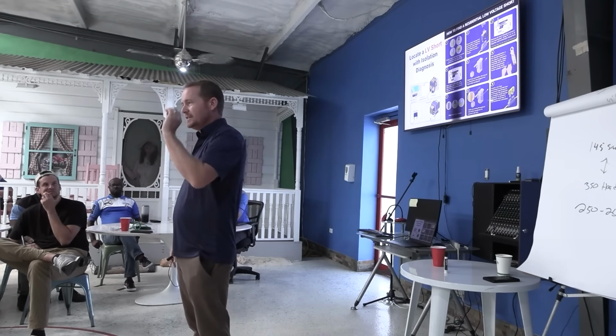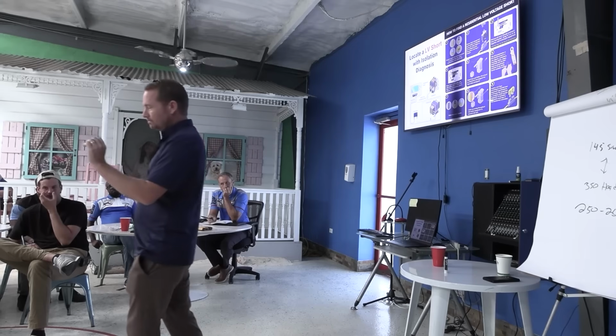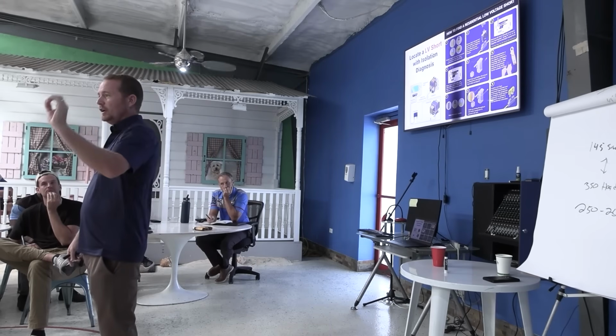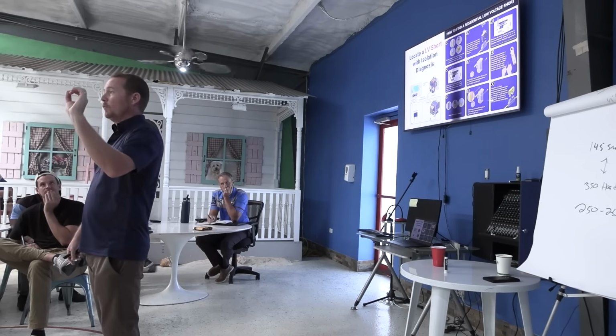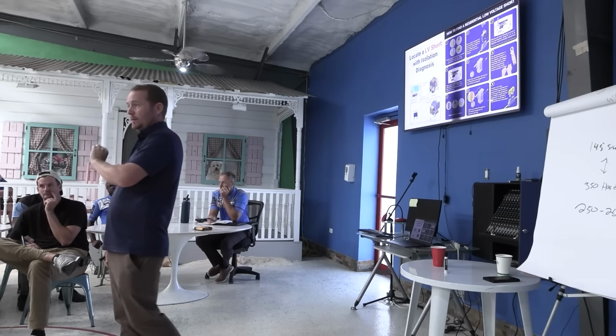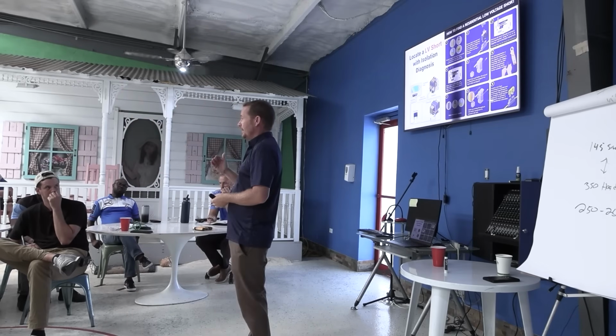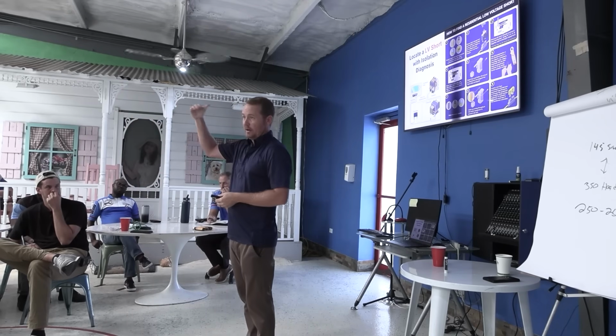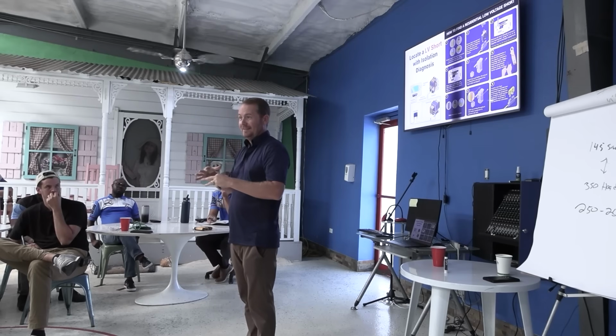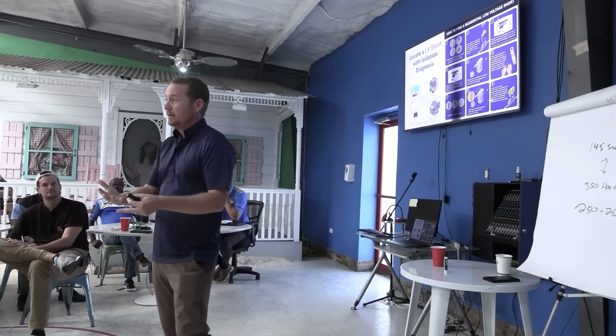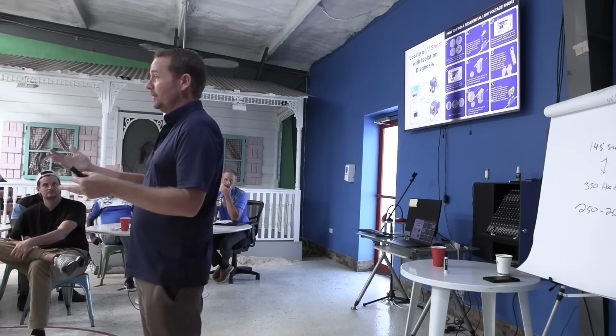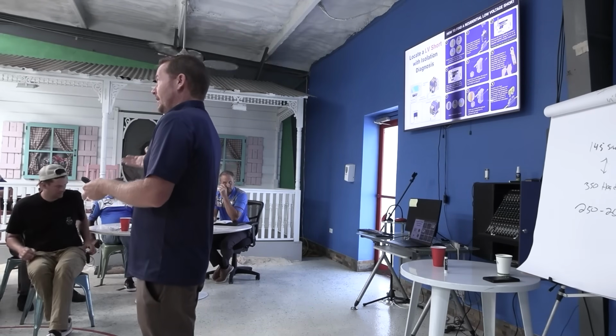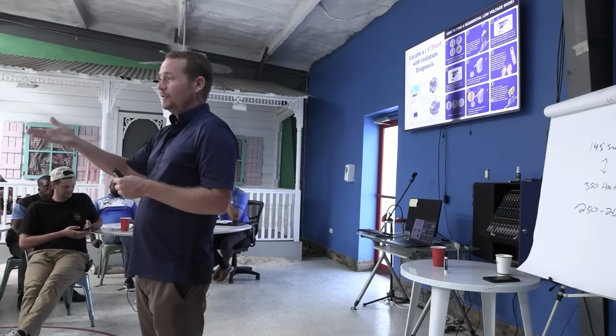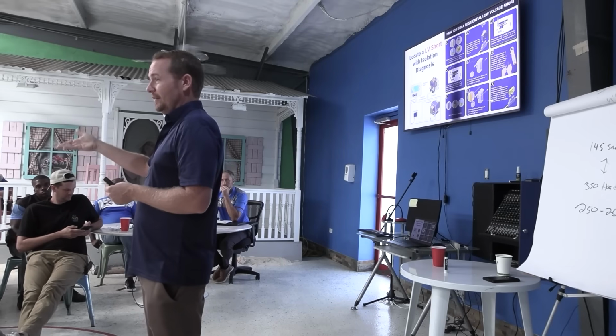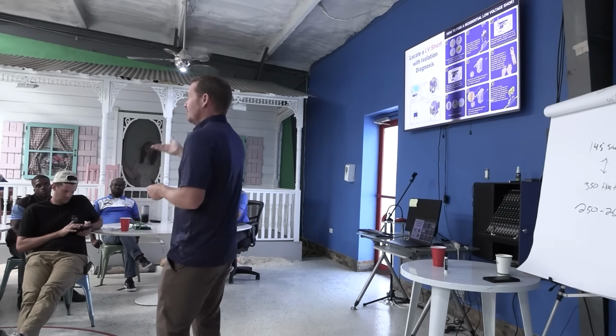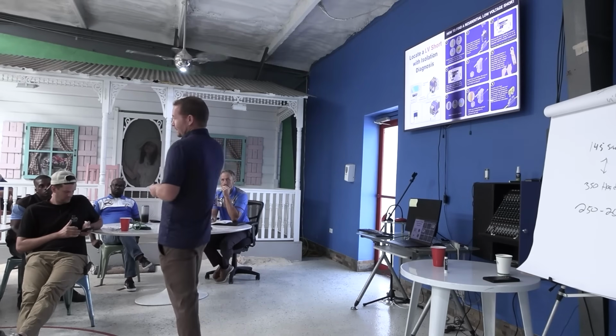But a short is a very particular thing. A short is anytime there is an undesigned path. And what causes a breaker to trip or a fuse to blow is current that is higher than the rating of that breaker or fuse. Make it simple: if you have a 30 amp breaker and it's tripping because the circuit is drawing more than 30 amps—if you have a 5 amp fuse that's blowing, it's blowing because the circuit is drawing more than 5 amps.